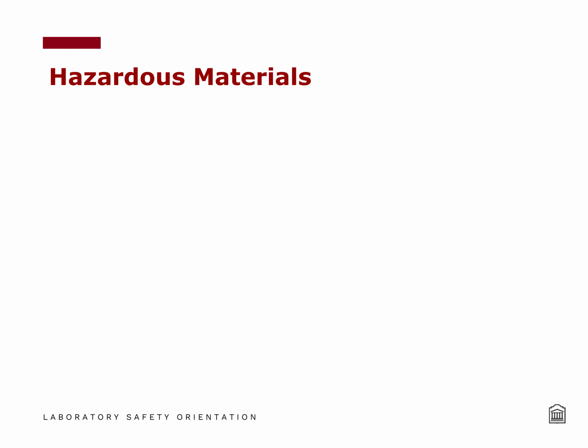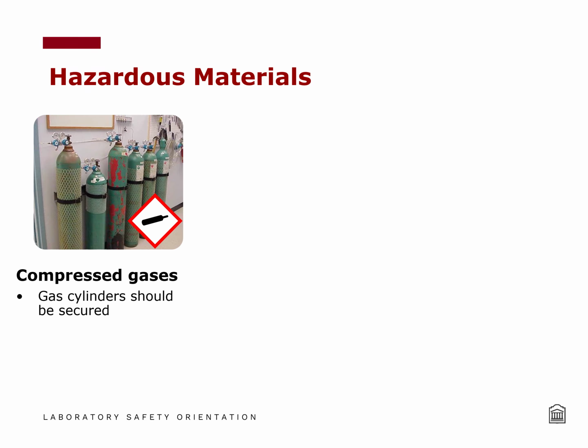Special consideration in labs should also be taken around compressed gases, flammable materials, and corrosive materials. In U Ottawa labs, compressed gases should be secured to the wall, either with a chain or individually. When they are not in use, they should be capped. The specific gas itself might have additional hazards. For example, flammable gases and oxidizers need to be stored separately, because together they can lead to fire and worsen that fire significantly. Coordination in this case is especially critical if you need to bring hazardous materials into a lab to complete your work. Gas cylinders must be moved away from flames and hot work because they can explode.